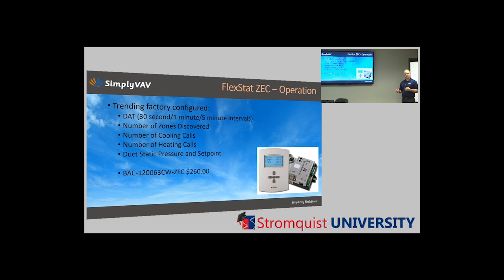So with that, do we have any questions about the zoning equipment controller or Simply VAV? How many zones did you say you can see at any one time? 16. 16? Right. There is an option. We do have an open program. So if you want to do something outside the box, you want to do 18 zones, or you want to do a custom instance range, or fan control if you got a VFD, we do allow that to happen in this same product. But out of the box, it will do 16 zones of zone controller.